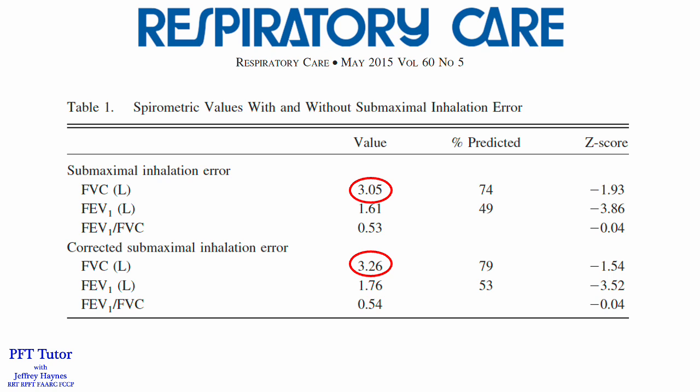However, this error had a significant impact on the forced vital capacity. When there was a submaximal inhalation error, the recorded forced vital capacity was 3.05, with a Z-score of minus 1.93. When the submaximal inhalation error was corrected, the forced vital capacity went up to 3.26 liters, and this became a normal value with a Z-score of minus 1.54.